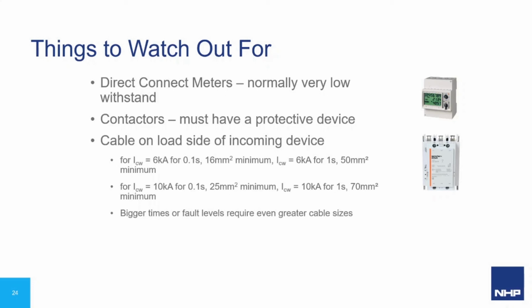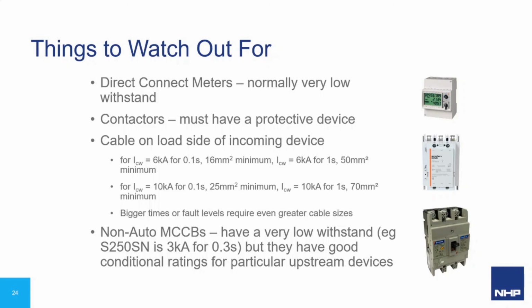The cable on the load side of the incoming device also needs to be considered. We can see some rough calculations here of how the fault level will increase the requirement of the incoming cable. A 6 kA for 0.1 second fault would require 16 mm² as a minimum. If we were to increase the time on this fault from 6 kA for 0.1 second to 6 kA for 1 second, it would increase the cable size to 50 mm². If we plan on using non-automatic devices as incomers, we need to be aware that they have a very low withstand and there are strict conditions on which they can be installed in higher fault level environments.